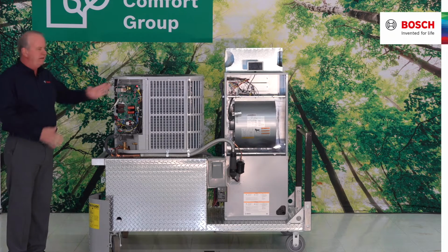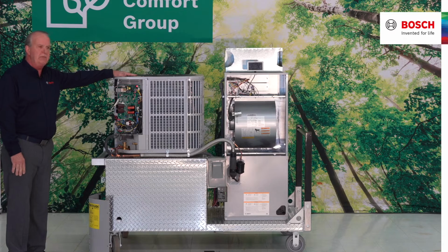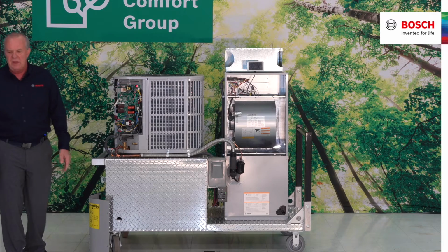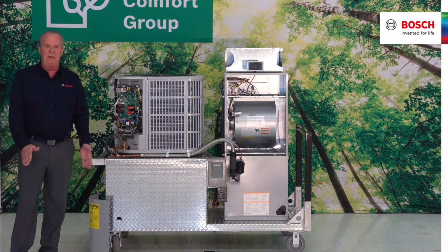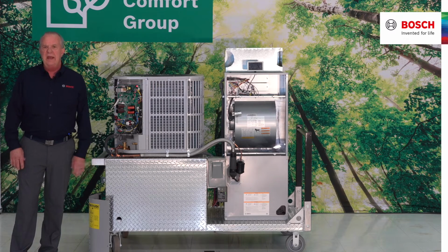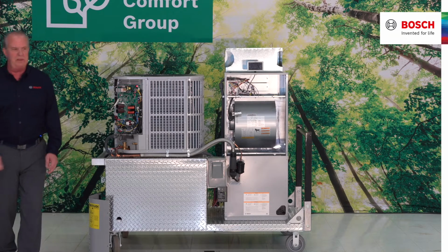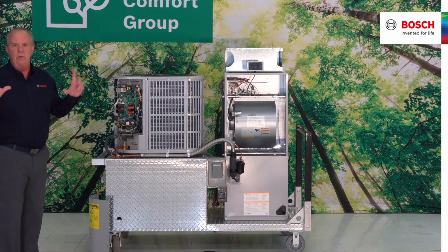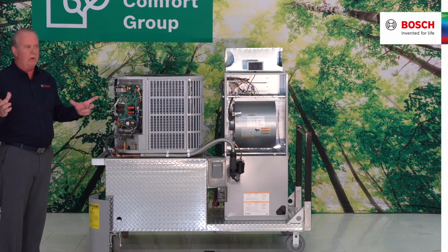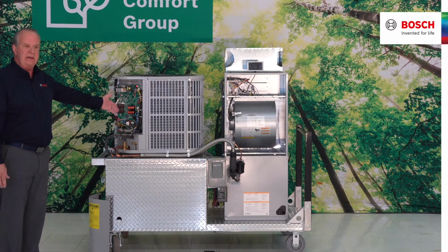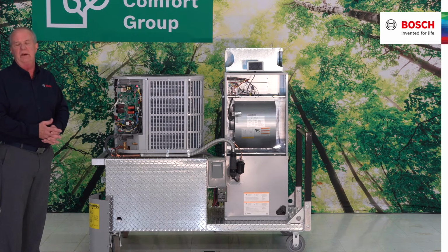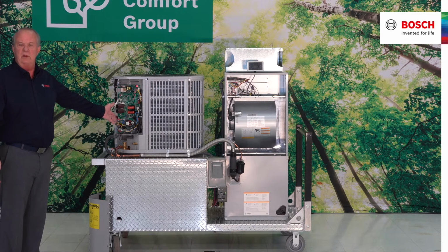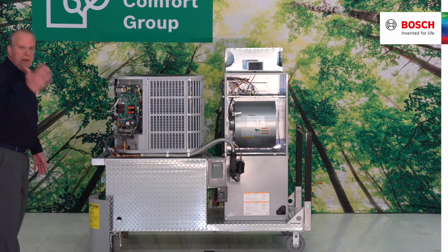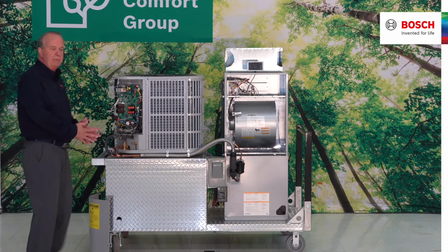Well, when I got to digging into this, I saw that the GMCC compressor on the 3-ton had a turn down capability of 9,000 BTUs, and a ramp up, if you will, or turn up capability to 44,000 BTUs. So that gives me that wide range from 9,000 BTUs to 44,000 BTUs. Technically, I can connect a 1.5 ton air handler to my 3-ton, an 18,000 BTU air handler, and this condensing unit will handle that without any problem, all the way up to a 36,000 BTU or anything in between.